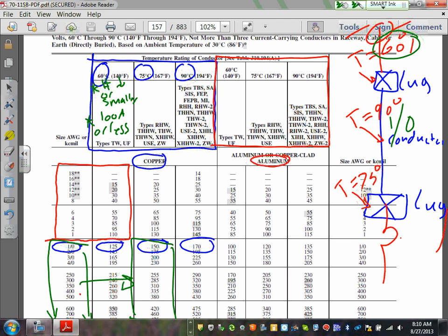Number one or smaller. Take this, a 60 amp panel, 120, 240. What size conductor do I need for this 60 amp? Which column are you going to default to? 100 amp or less, where do you go? 60. Did you guys hear me? 100 amp or less, where do you go? To 60. No question asked. Okay, another default.